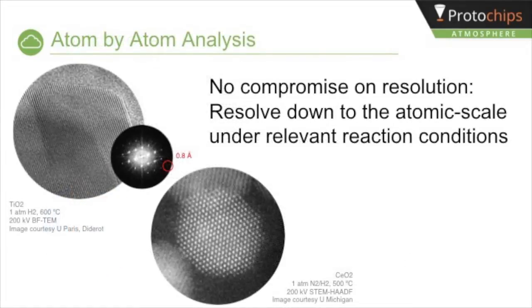Atmosphere maintains instrument resolution under high pressure and temperature, enabling atom-by-atom analysis. The left figure is a bright-field TEM image of titanium dioxide taken at 1 atm of hydrogen and 600 degrees Celsius. An FFT of the image, shown in the inset, indicates a lattice resolution of 0.8 angstroms, demonstrating the ultra-high stability of Atmosphere.